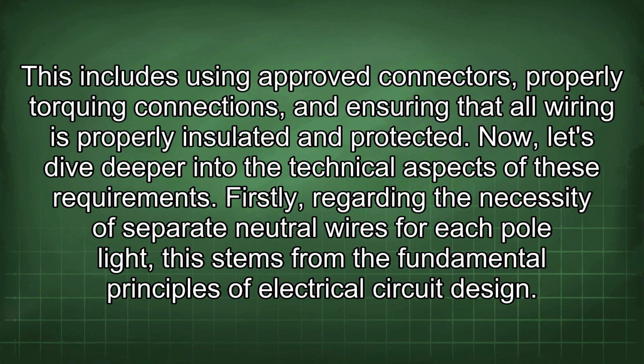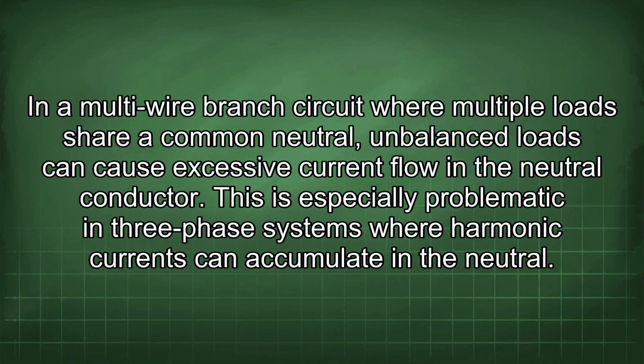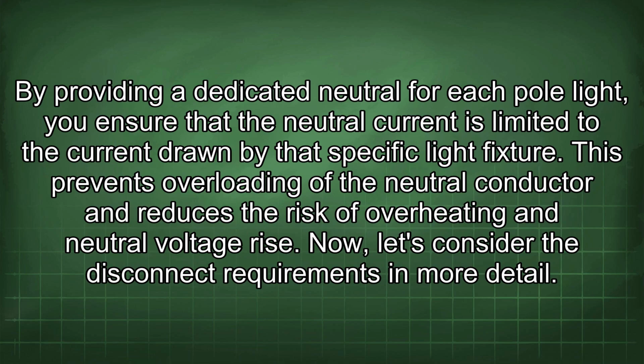Firstly, regarding the necessity of separate neutral wires for each pole light, this stems from the fundamental principles of electrical circuit design. In a multi-wire branch circuit where multiple loads share a common neutral, unbalanced loads can cause excessive current flow in the neutral conductor. This is especially problematic in 3-phase systems where harmonic currents can accumulate in the neutral. By providing a dedicated neutral for each pole light, you ensure that the neutral current is limited to the current drawn by the specific light fixture. This prevents overloading of the neutral conductor and reduces the risk of overheating and neutral voltage rise.